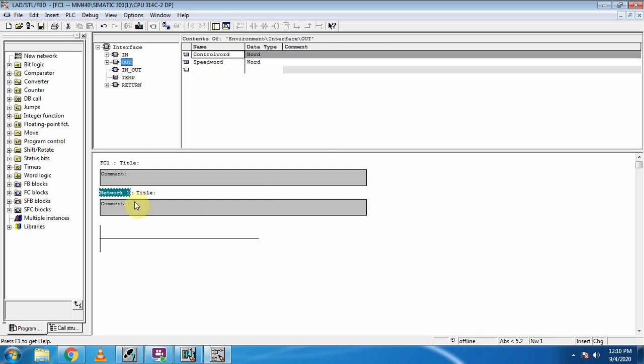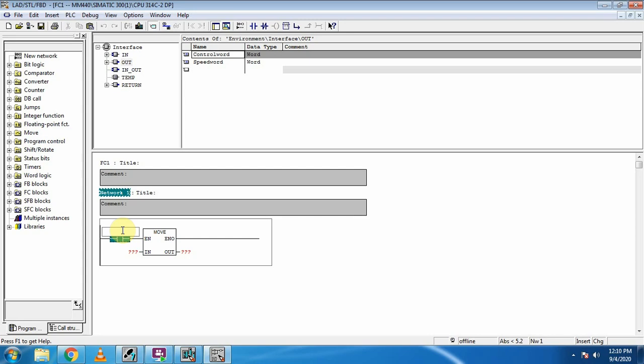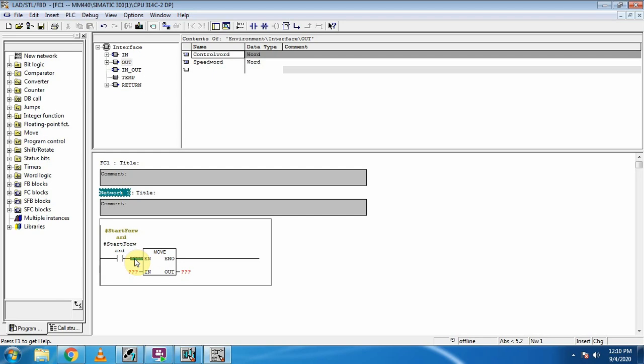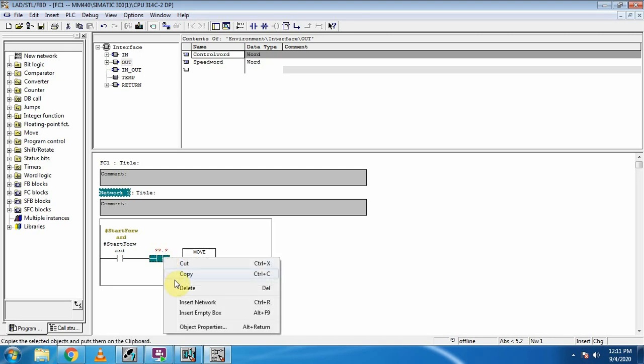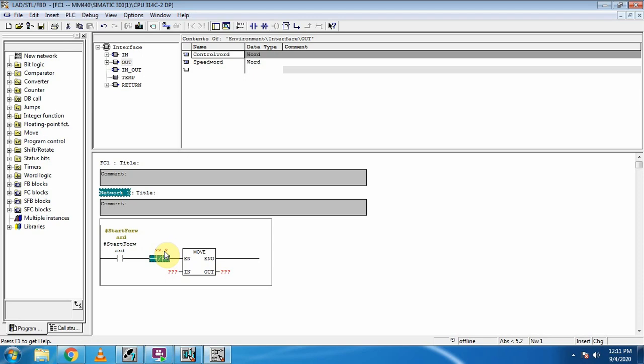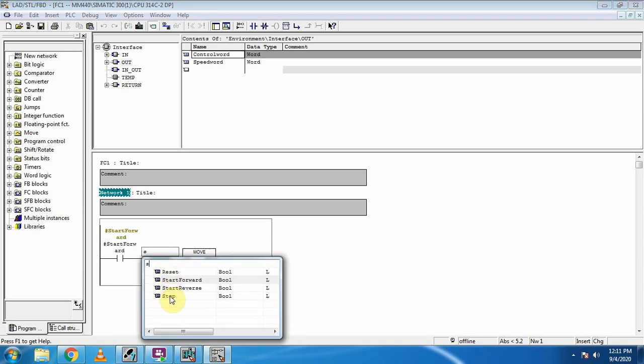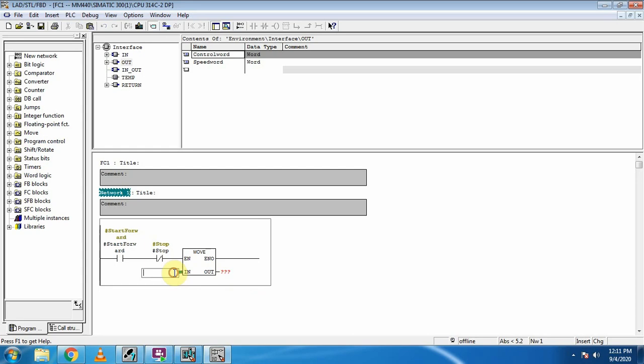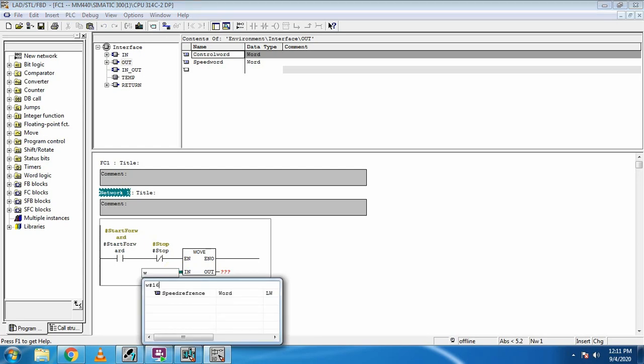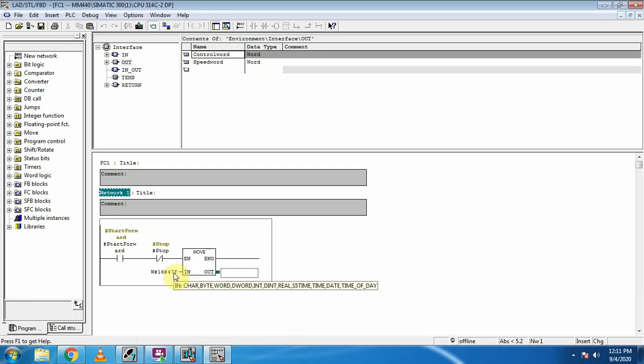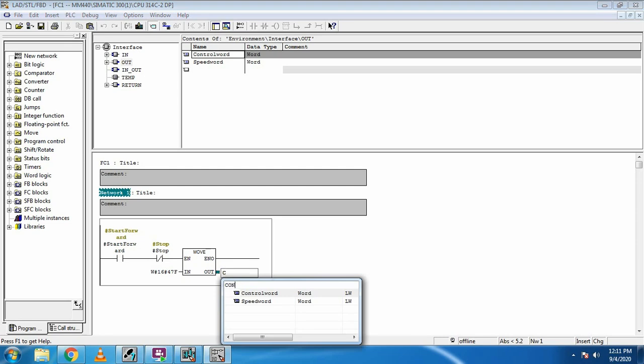In the ladder logic we take one normally open bit, write 'start forward', and use the normally closed contact of the stop input. To run the motor in the forward direction, we write the code 047F and transfer it to the control word — this runs the motor forward. So if we turn on the start forward bit, it will send the 047F code to the control word, and the VFD will run the motor in the forward direction.